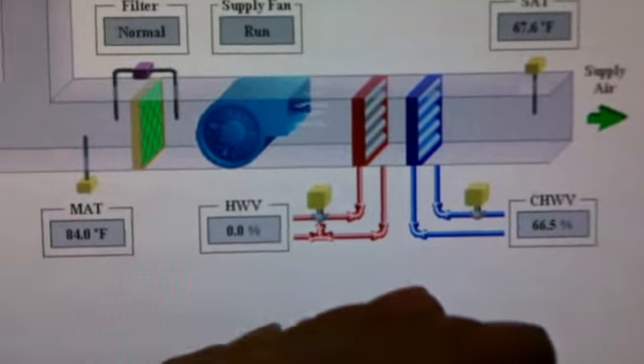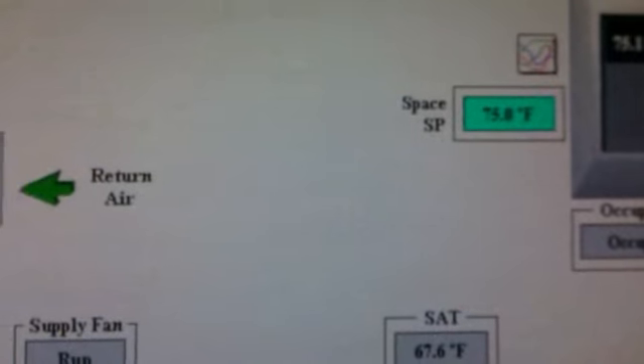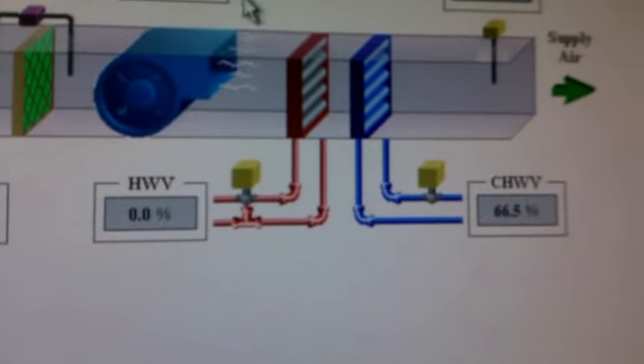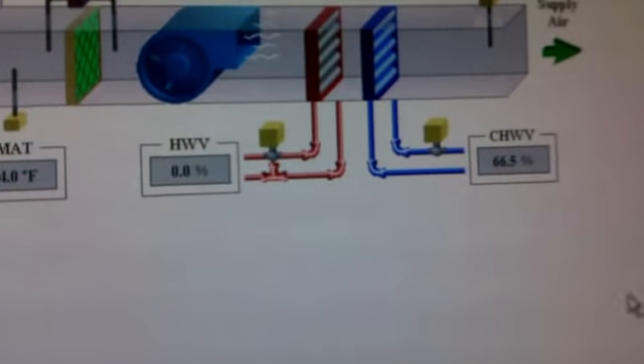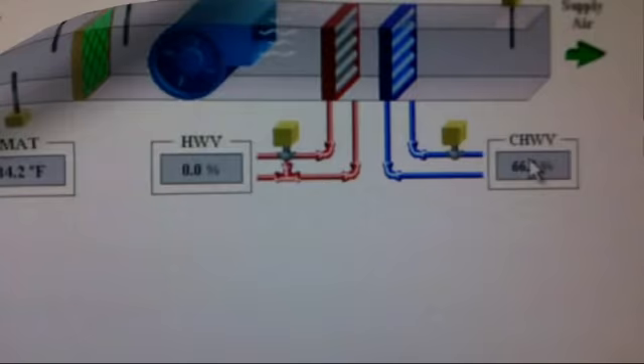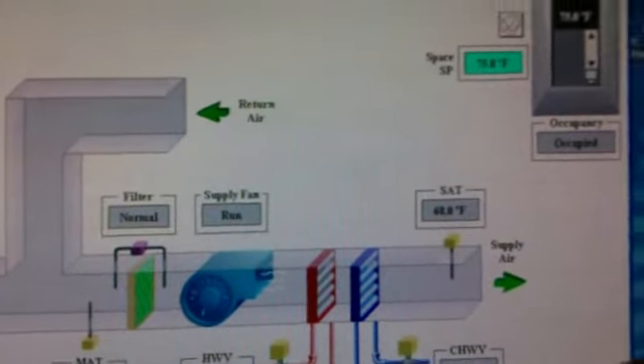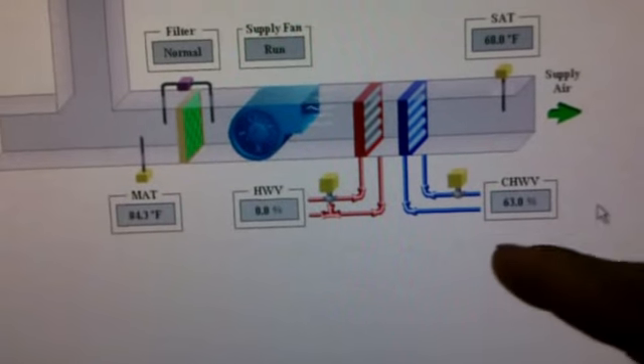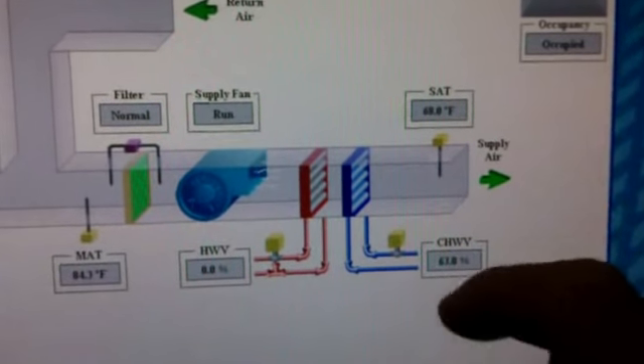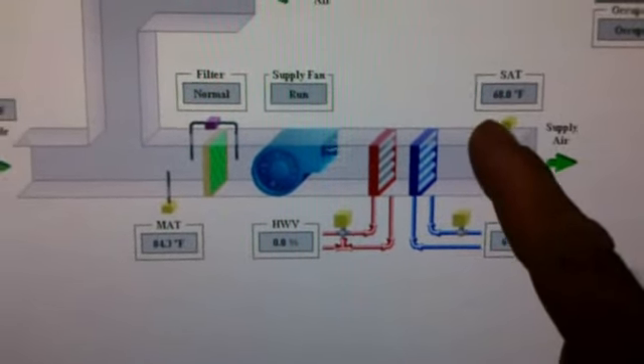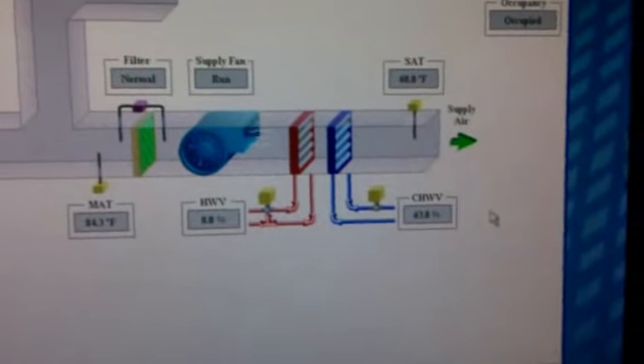And I got this loop program pretty good to where it just adjusts the valve open and close just enough to keep a steady room temperature, instead of just blasting out 56 degree air and then turning it off, and then 56 degree air 10 minutes later turning it off, to average out the space temp. These modulate the valve for consistent supply. So these, like I said, now it's down 75 dead on. Like I said, the valve is modulating a consistent output of what it takes to maintain room temperature. So it's putting out 68 degrees right now with the current load in the room to maintain set point. So it's sweet. You can look at the trends and see what it's been doing.